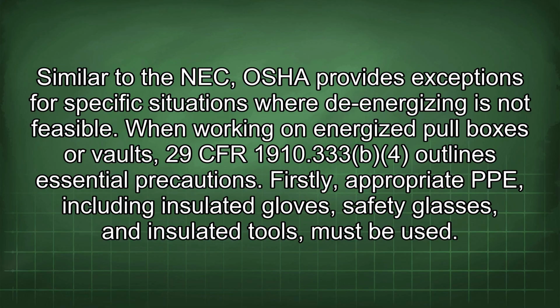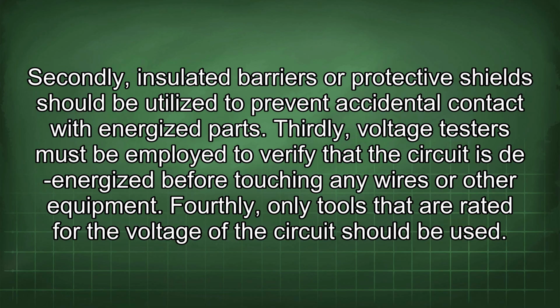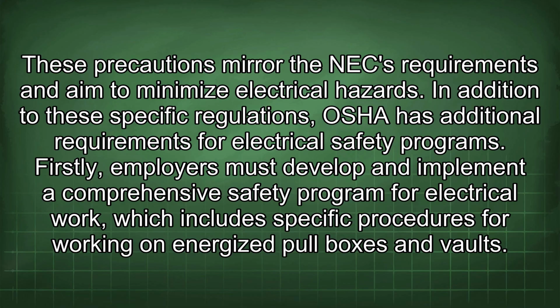When working on energized pull boxes or vaults, 29 CFR 1910.333 outlines essential precautions. Firstly, appropriate PPE, including insulated gloves, safety glasses, and insulated tools, must be used. Secondly, insulated barriers or protective shields should be utilized to prevent accidental contact with energized parts. Thirdly, voltage testers must be employed to verify that the circuit is de-energized before touching any wires or other equipment. Fourthly, only tools that are rated for the voltage of the circuit should be used. These precautions mirror the NEC requirements and aim to minimize electrical hazards.